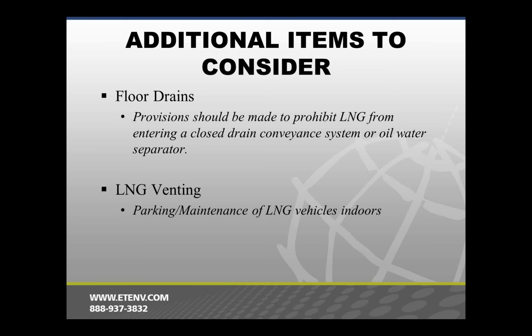If you have open drains, there's a pretty good argument for doing nothing, but it needs to be addressed on a case-by-case basis. The other thing for shops, LNG vehicles in shops, is that they will spontaneously vent when pressure builds in their tank just due to normal heat gain. Code requirement is at least 3 days minimum hold time on those tanks. However, once you exceed that pressure in the tank just from normal warming, it's going to spontaneously vent inside your shop. And so there are some code requirements. NFPA 52 addresses it, in Chapter 15, that you need to be able to mitigate that hazard. What it doesn't say is how you do it. So there are differing opinions there, but we think there's a solution within reason.